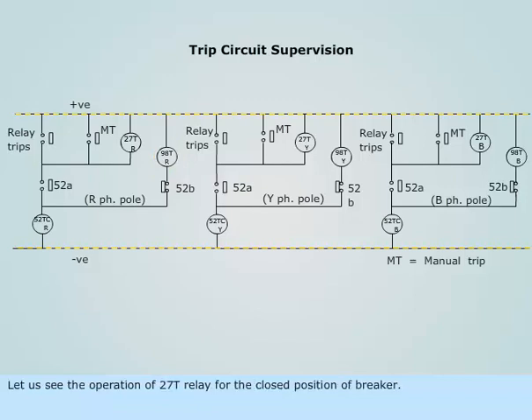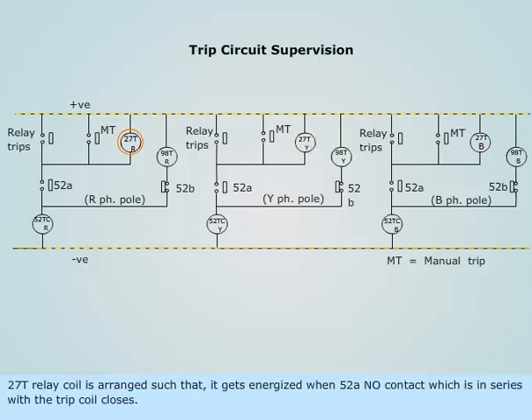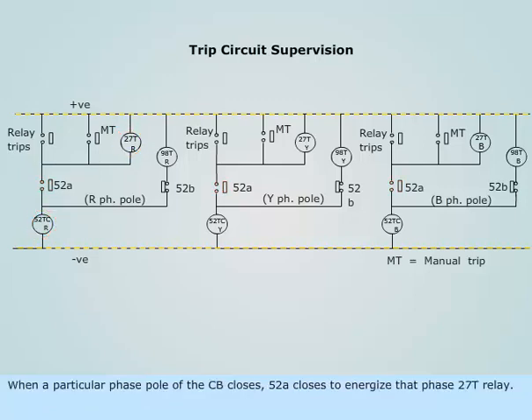Let us see the operation of 27T relay for the closed position of the breaker. The 27T relay coil is arranged such that it gets energized when the 52A NO contact, which is in series with the trip coil, closes. When a particular phase pole of the CB closes, 52A closes to energize that phase's 27T relay.